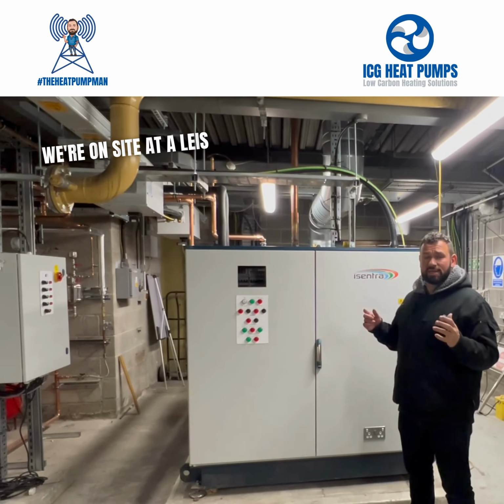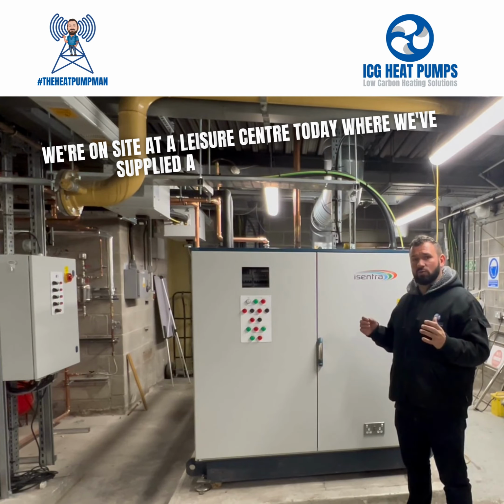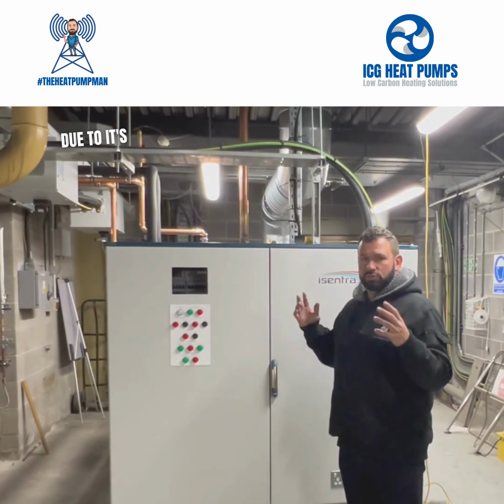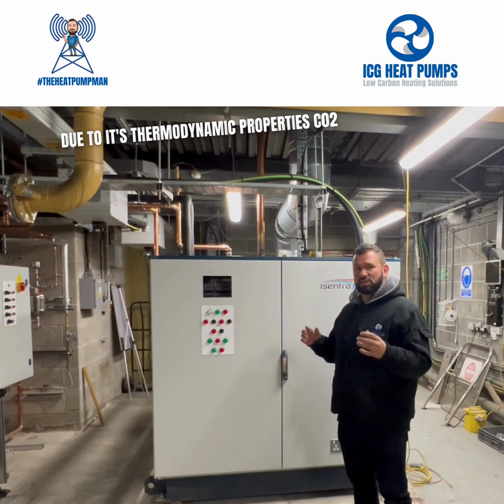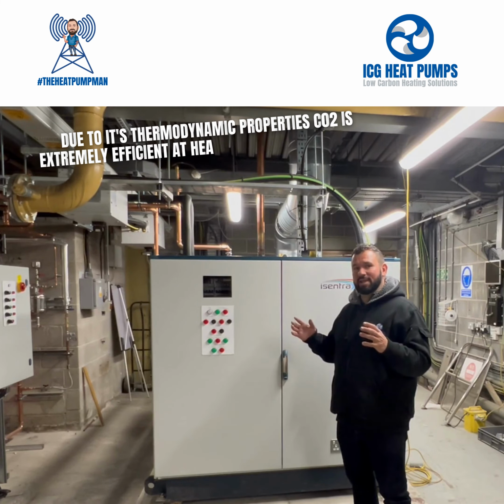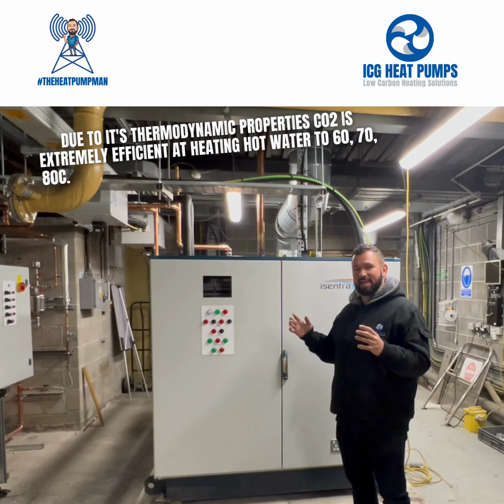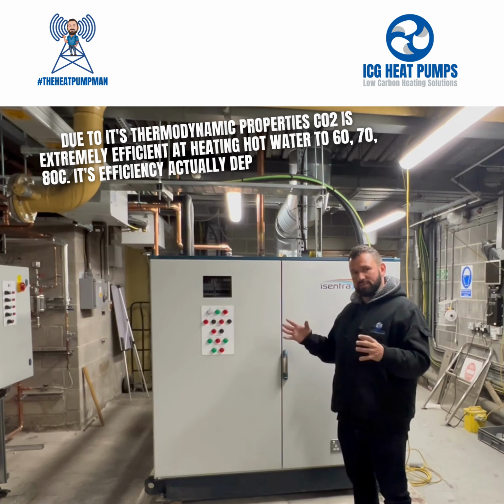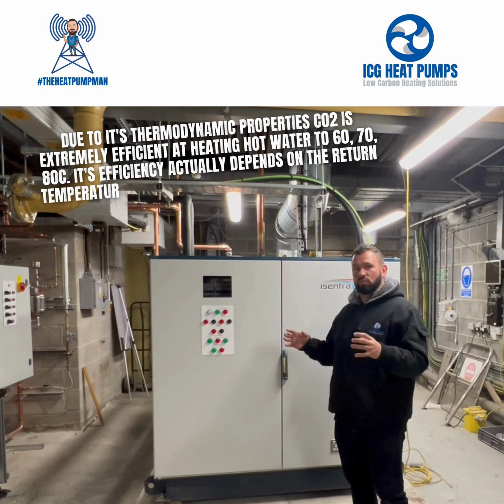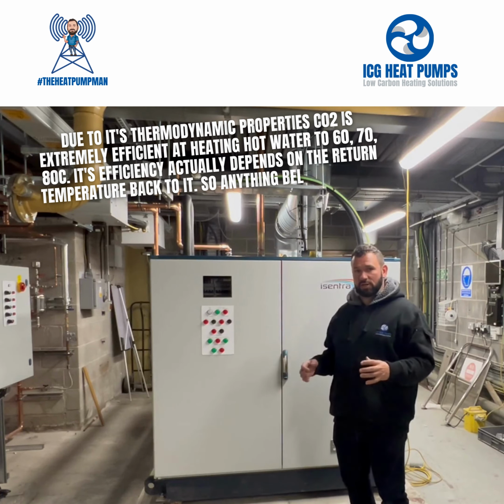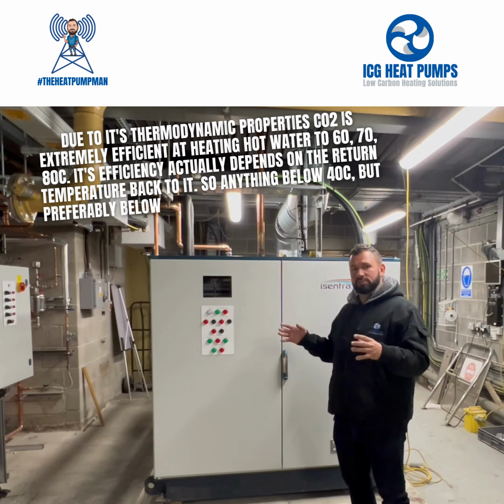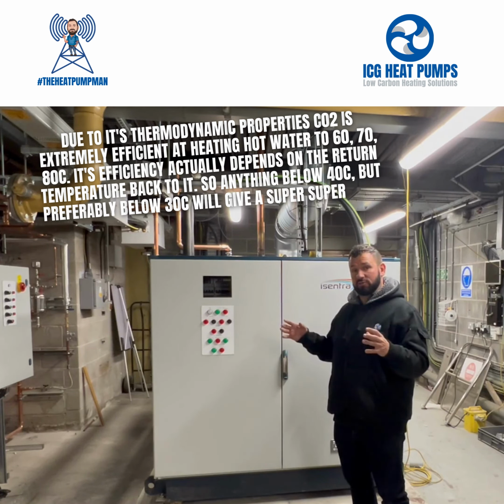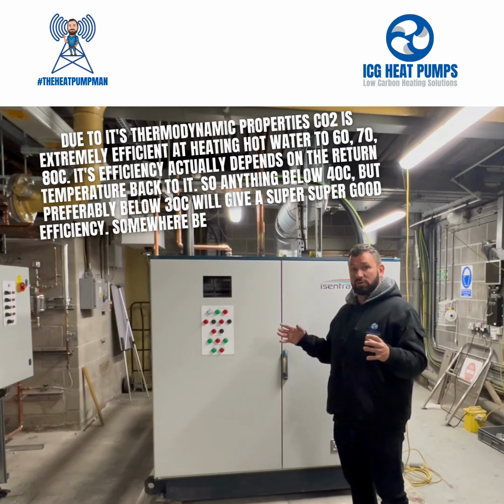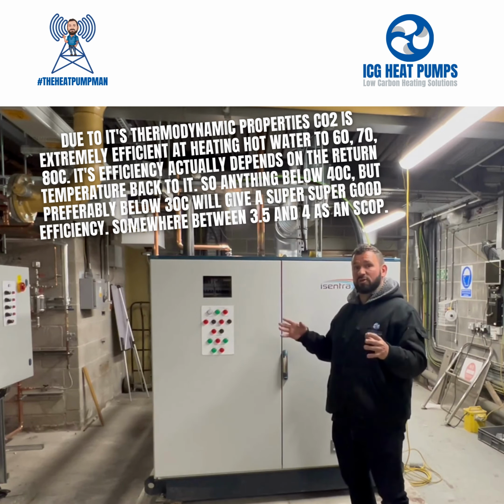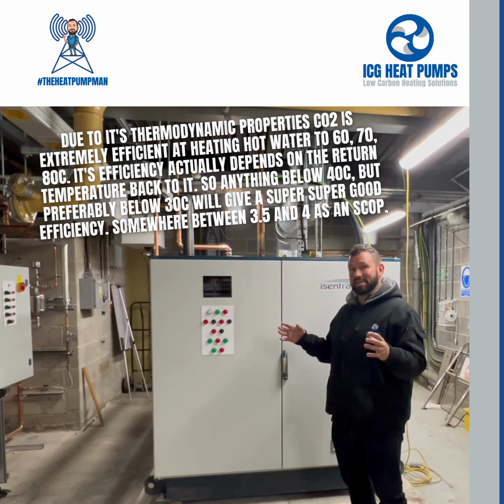We're on site at a leisure centre today where we've supplied a 200 kilowatt CO2 heat pump. Due to its thermodynamic properties, CO2 is extremely efficient at heating hot water to 60, 70, 80 degrees. Its efficiency actually depends on the return temperature back to it. So anything below 40 degrees, but preferably below 30 degrees, will give a super good efficiency, somewhere between 3.5 and 4 as an SCOP.